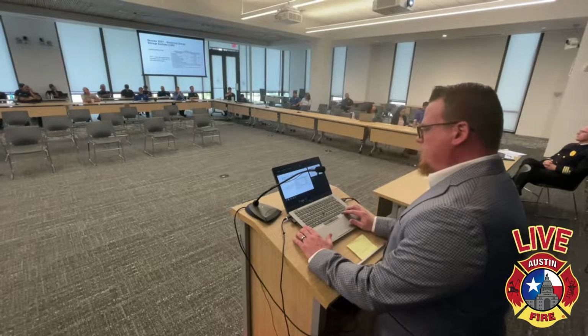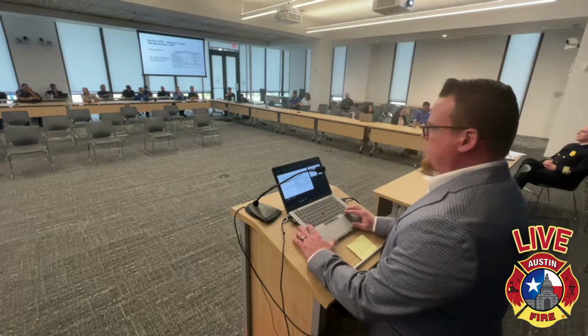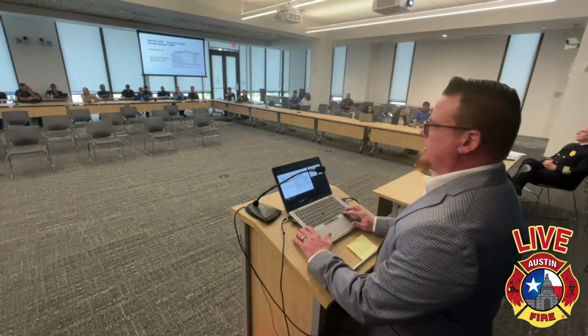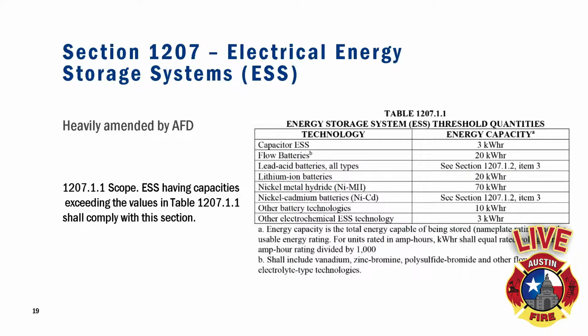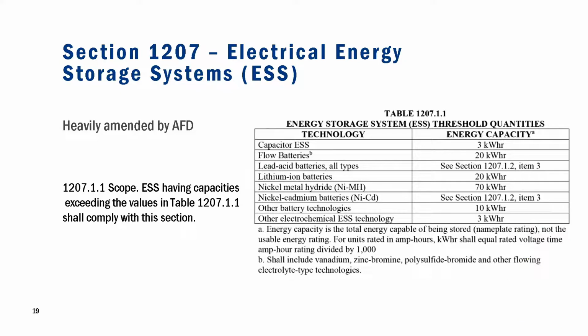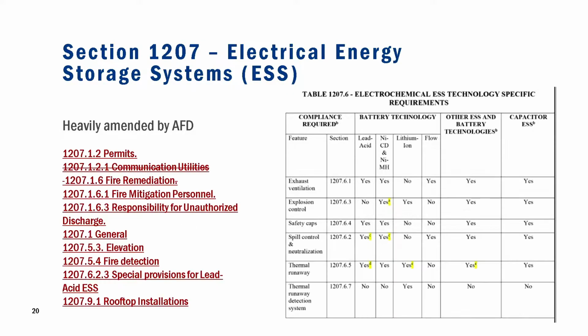So Section 1207 was electrical energy storage systems. Typically what we're seeing a lot of these days is lithium ion or some of those hybrid salts. So this was heavily amended by our hazmat group, and this table here essentially is if you're exceeding these capacities, then you have to follow the provisions similar to what the old 608 was, and these thresholds are the same as what were listed in the reportable quantities limit at the front. So if you're below this, no hazmat permits required. If you hit this, then a hazmat permit's required, and then you have to follow the provisions of the code. As I said, this was heavily amended.